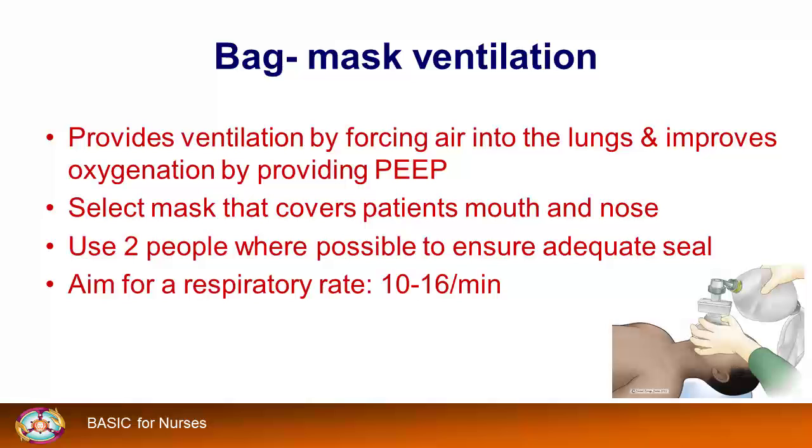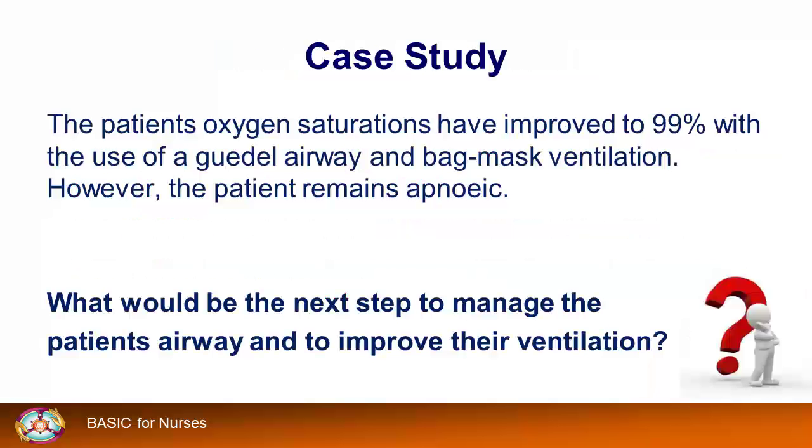Ensure you don't squeeze the bag too hard and cause the overdistension of the lungs. A self-inflating bag can deliver a tidal volume up to 2 litres, when most patients only require 300 to 500 mils. Aim for a respiratory rate of 10 to 16, so about 1 breath every 4 to 6 seconds.